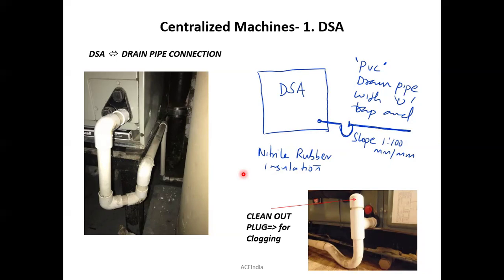These pipelines are carried in the plenum area. In the same plenum area, you have your return air, and this return air consists of moisture content. So this moisture will contact the pipe surface, and it can form water droplets on the surface of the entire pipe system. In order to prevent that, you need to provide some kind of insulation on the drain pipe connections. So that is why we use nitrile rubber foam insulation, especially for the drain pipe and even for the copper pipes. Okay, so is it clear? Clear, guys?